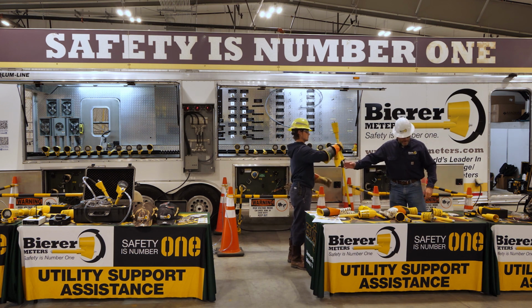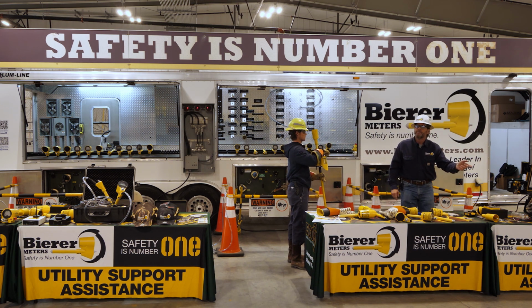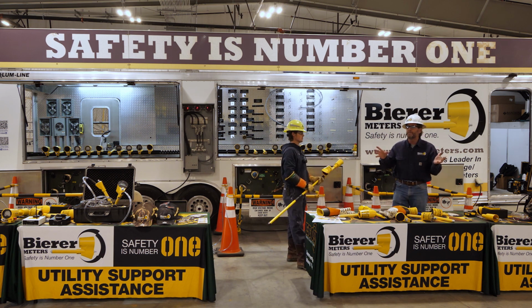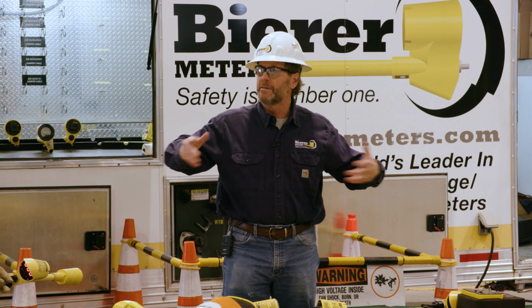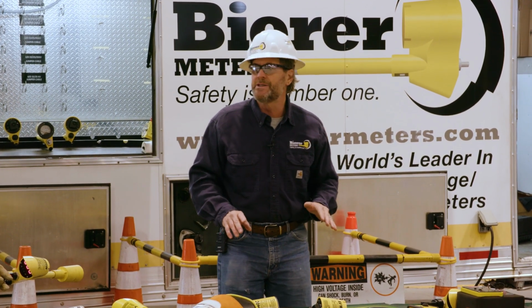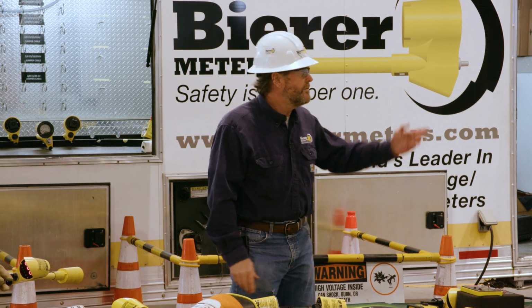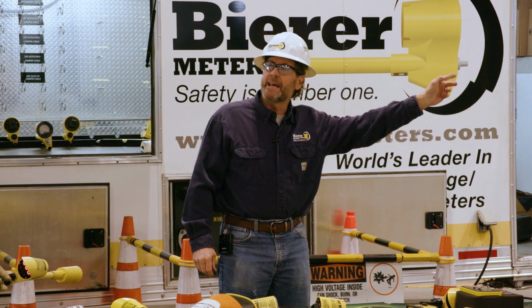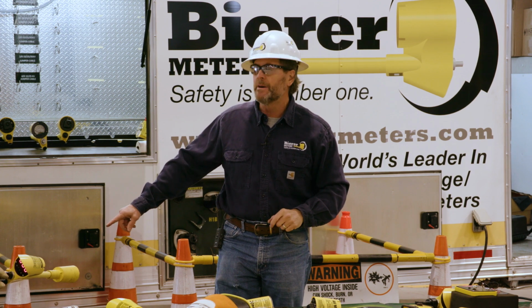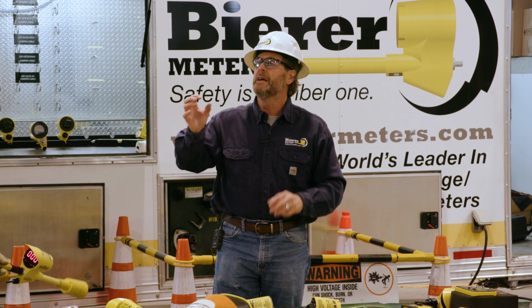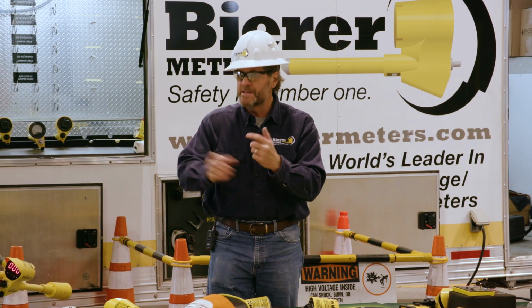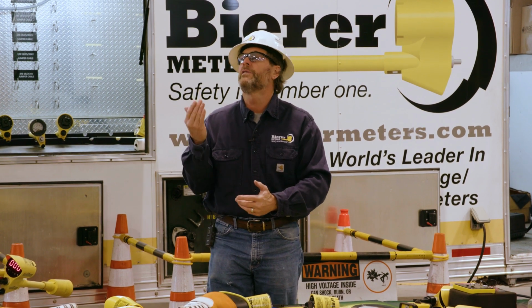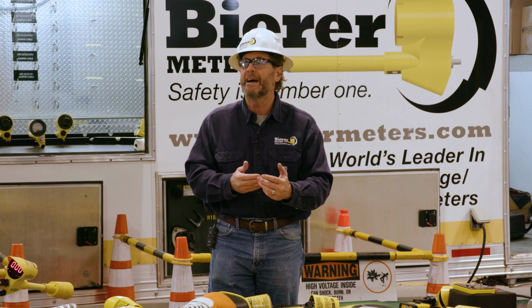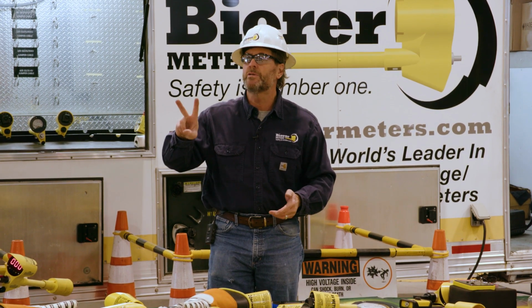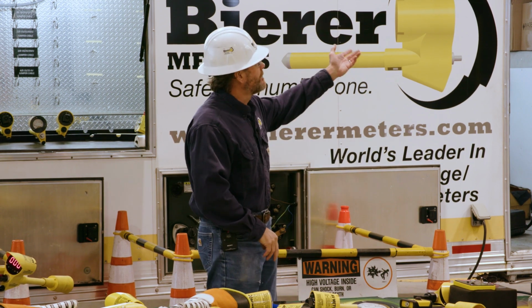Here you go, bud. All right, so the reference probe, we're going to go to an A phase. Now, you guys know that 3 phases come out of that generation plant. Your leading phase, that's your 0, whatever you choose it to be. Here we're referencing the A phase as our leading phase, so if Robbie touches any phase over here, regardless of potential, and it's an A phase, then it's the same phase. So we'll have a white light here if it's energized, and if it's the same phase, Mr. Robbie's going to see a white light on the meter, the PD800W. He's going to see a white light, and he's going to see the numbers, the LED display, saying close to 0. It could be a little under, it could be a little over, depending on leading and lagging power factors. It could be, but it's going to be close. So he'll get 2 confirmations that it's the same phase. If A is our reference, that's our 0.